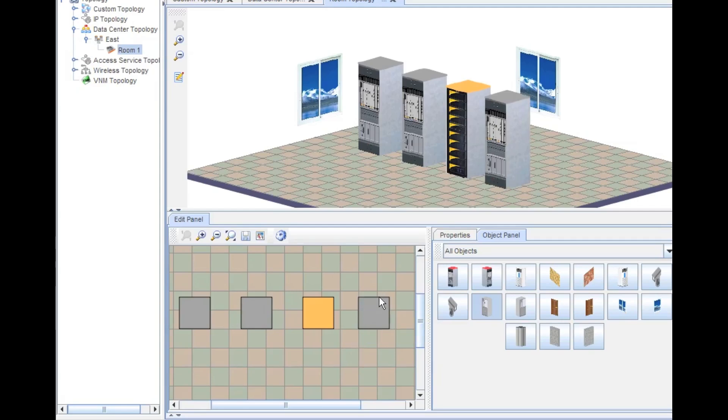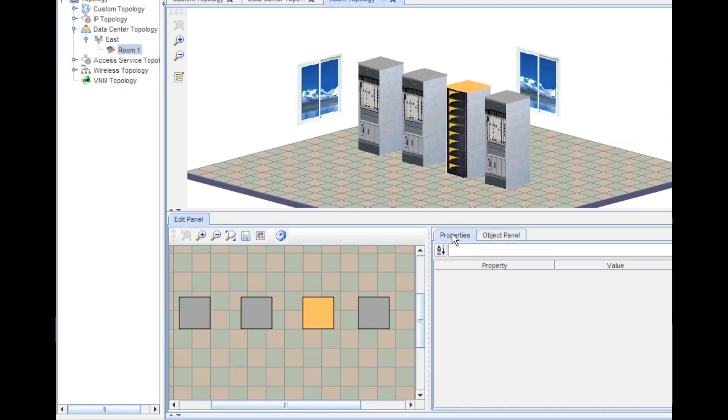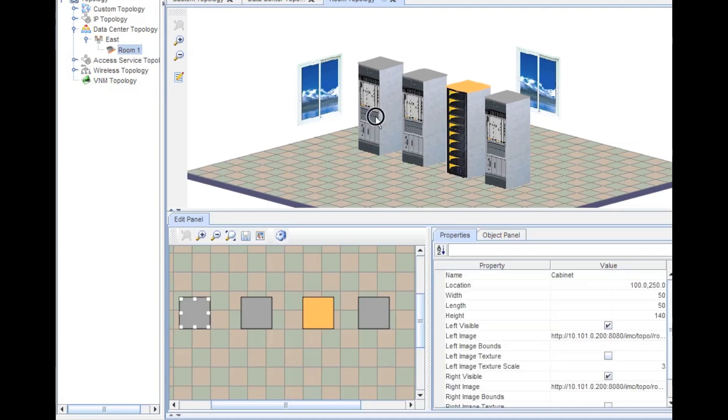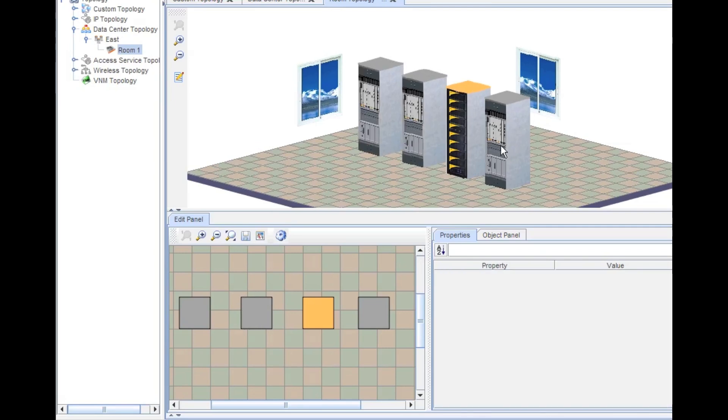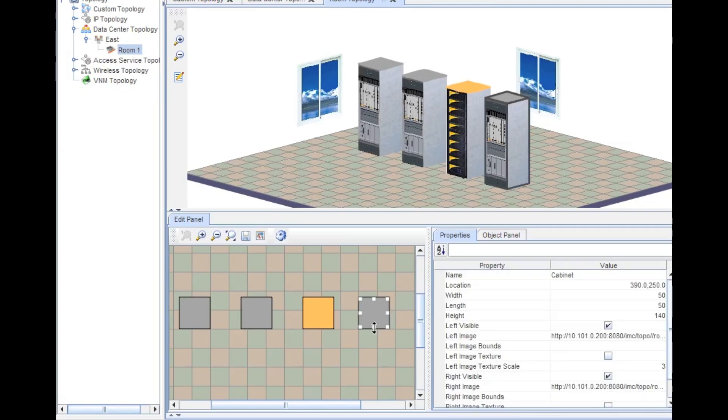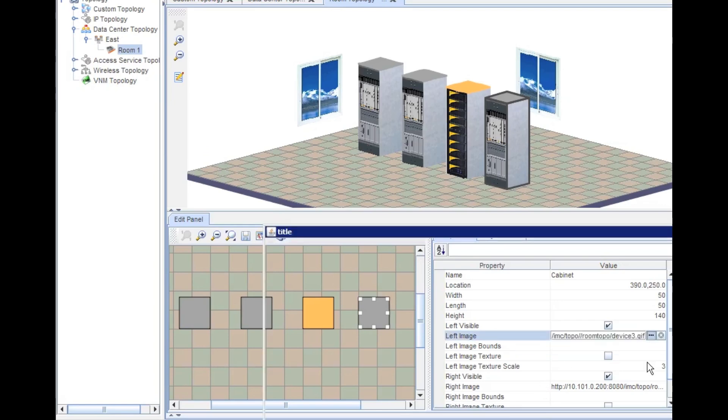We can also add a cabinet in here. The nice thing about the cabinet is it is alive, so it will always take on the color on top. You can see the one that we've got is orange. It will take on the color of the device in the cabinet with the highest level of alarm. In this case, we can see we got orange, which is a major alarm.